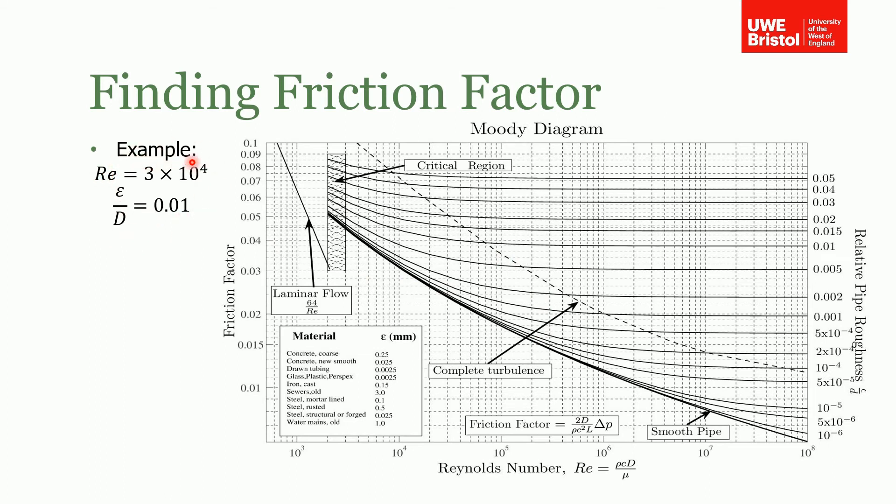Let's say in this example we have a Reynolds number of three times ten to the four and a relative roughness of 0.01. How do we find the friction factor? Well, the first thing is we look up the Reynolds number on here: one times ten to the four, two times ten to the four, three times ten to the four. We also look up our relative pipe roughness, which is this line here. Remember, this is a line of constant pipe roughness. We just need to find the point where these two intersect. We keep following this line until we get to this point here. That is the point, the middle of those crosshairs, where those two lines intersect. We then read off on the left-hand scale the friction factor, which in this instance is 0.04.